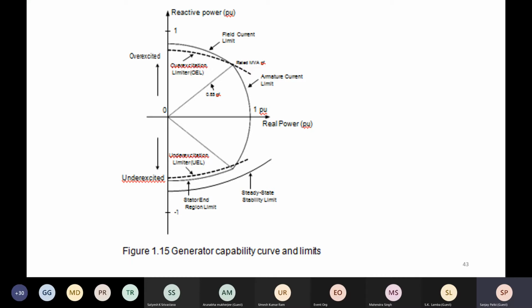In some hydropower systems where there is an on-load tap changer on the generator transformer, you may also resort to on-load tap changing operation so that reactive power export can come down. Or on the grid side, if reactive power sources are available, then the grid operator, that is the load dispatch center, will take action on the network side so that the voltage level will improve and your reactive power generation requirement will become lower. Overriding all this, normally we recommend that an over-excitation alarm should be set at a 10% lower level. So if this is your capability limit, the over-excitation limiter is set at this in the AVR, that is the automatic voltage regulator, and 10% below that you should have an alarm so that you will be alerted that you are approaching the over-excitation limiter.